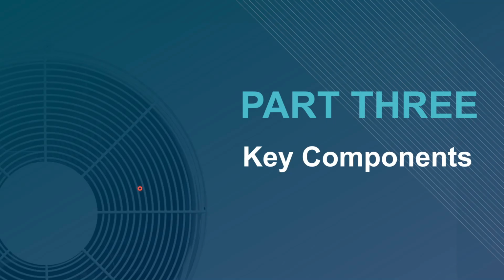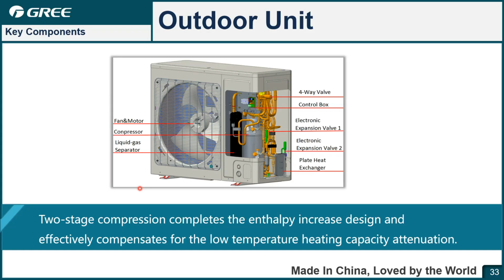Second part, I will share some information about key components. The first one is the split type outdoor unit. When you open the panel of the outdoor unit, you can see there are many components inside, such as the compressor, fan motor, and this one is the liquid gas separator. Then on the right side there are the plate heat exchanger, expansion valve 2, and expansion valve 1. For these two expansion valves, their functions are different. This is for the major refrigerant pipe throttling. This is for the economizer.